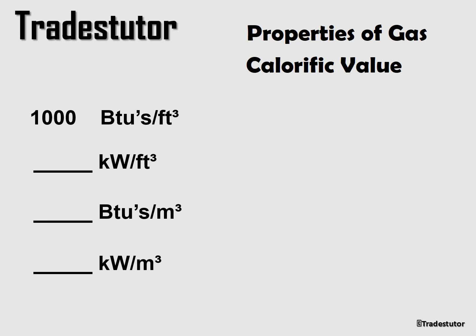For the first conversion — BTUs per cubic foot to kilowatts per cubic foot — the volume stays the same, so we just need to convert BTUs into kilowatts. We use the fact that 3412 BTUs equals one kilowatt. Dividing 1000 by 3412, we end up with 0.293 kilowatts per cubic foot.